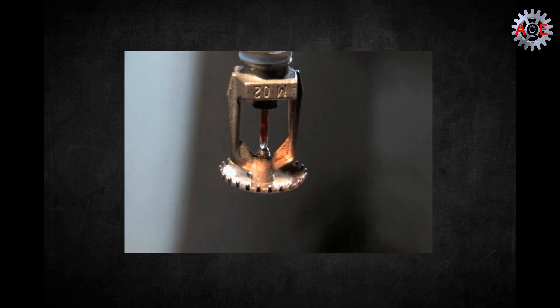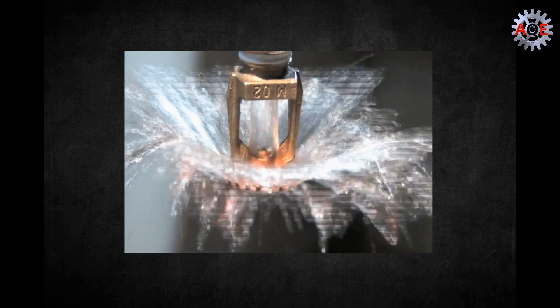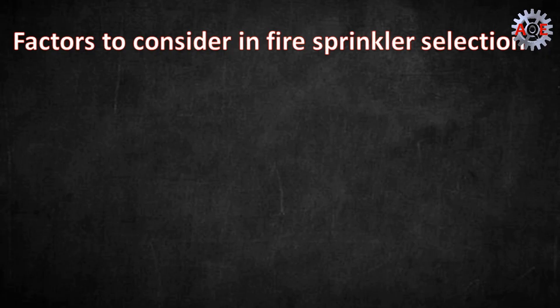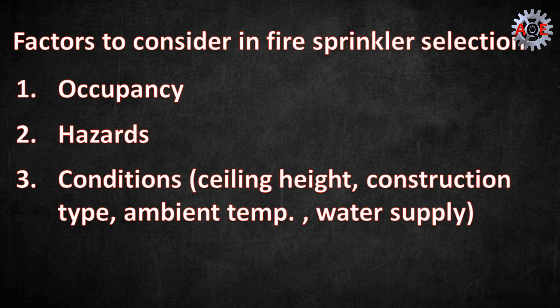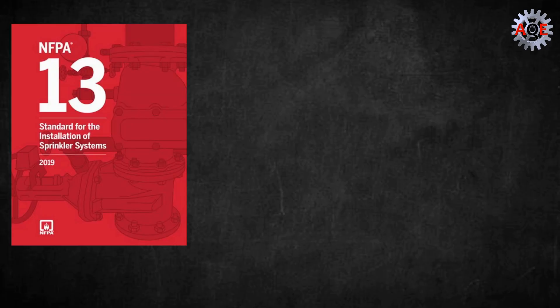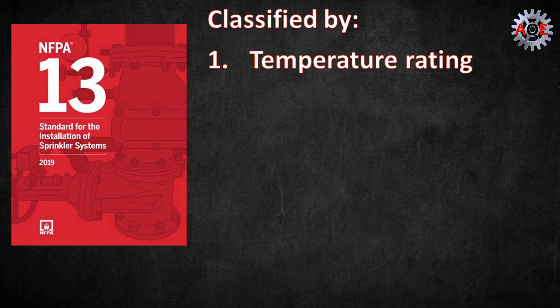Choosing the right fire sprinkler is critical to the success of a sprinkler system in controlling or extinguishing a fire. Sprinklers should be chosen by evaluating occupancy hazards and conditions, ceiling height, type of construction, ambient temperature, available water supply, and more. Sprinklers are classified by NFPA 13 standard for the installation of sprinkler systems in several ways, including temperature rating, K-factor, orientation, response type, design and performance characteristics, and special service conditions.